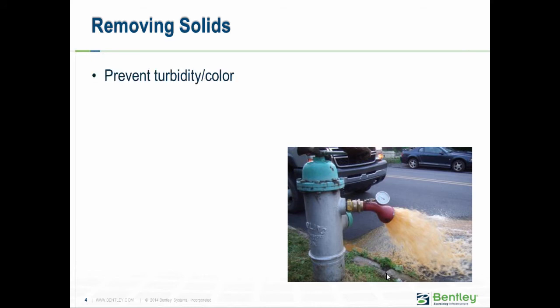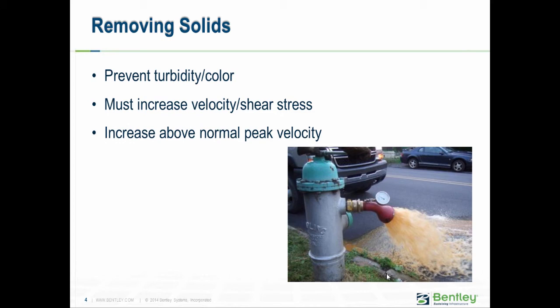Removing solids in the distribution system — in this case, we're trying to prevent turbidity or color. We don't want the water to be cloudy or have color. The key is velocity, or really shear stress. You want high shear stress along the pipe wall, which is going to stir up solids and move them out of the system. The key goal is to increase velocity above normal conditions — for example, if solids settle at 0.5 feet per second, you need to get well above that. You also want to flush with clean water behind you, bringing water from a part of the system that is of relatively good quality.